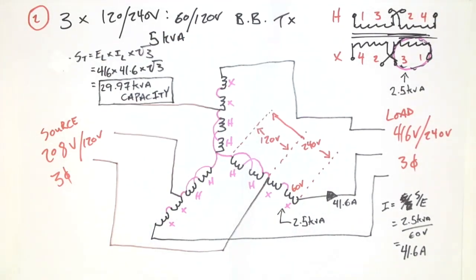So notice we used 3 5 kVA transformers, and we are able to drive almost 30 kVA worth of load. So that's a substantial cost savings. Substantial when compared to a typical standard isolation type transformer. All right, well, let's take a look at another example.